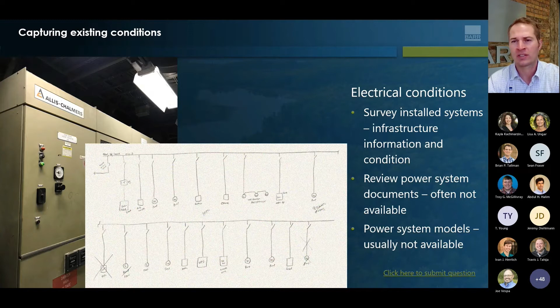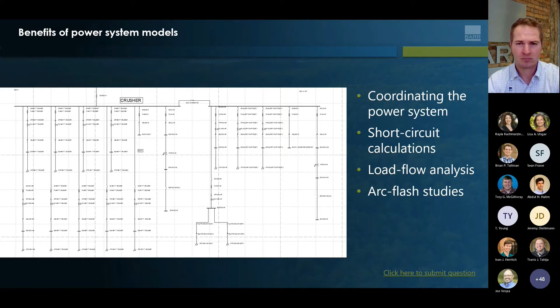The model is useful for coordinating of the power system, specifically with new infrastructure going in. It's used for producing the short circuit calculations, load flow analysis, and then completing arc flash studies. So speaking of coordination, if coordination isn't done properly, trips can occur at the wrong level. So one of our clients' underground facilities experienced such a thing on a system that was not modeled up. They had a single line diagram for the facility, but no power model.